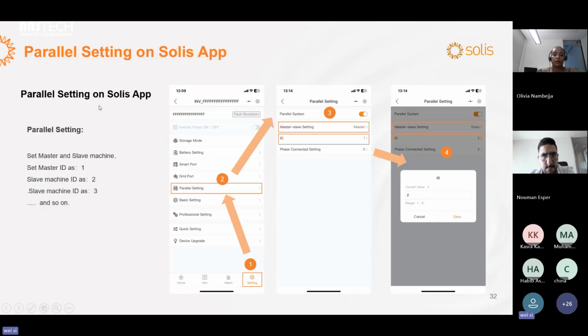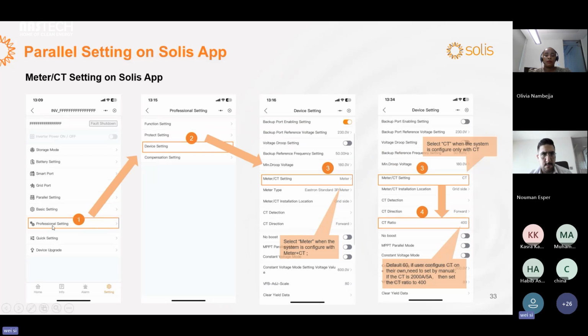It is about the parallel setting on the Solis app. It is the same operation as on the inverter screen. Enable the parallel system, then choose which one is the master and which one is the slave, and set the physical ID. For example, the master ID is 1, then the slaves are 2, 3, 4, 5. Then choose the professional setting, devices setting, then choose the meter or CT setting. If you have only a CT, you just need to set it as the CT. If you have the meter and the CT, just choose the meter option. Then set the CT ratio.